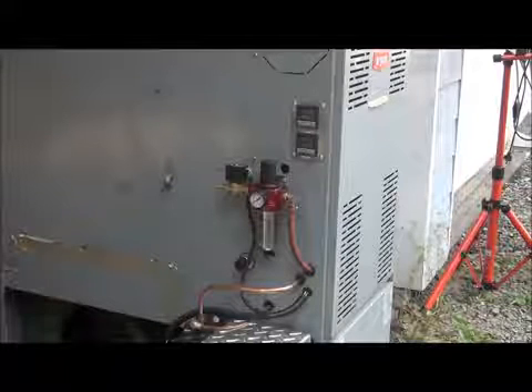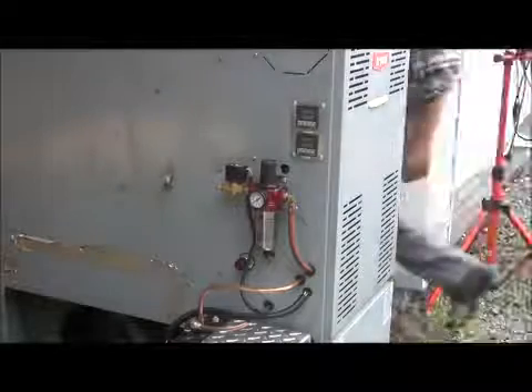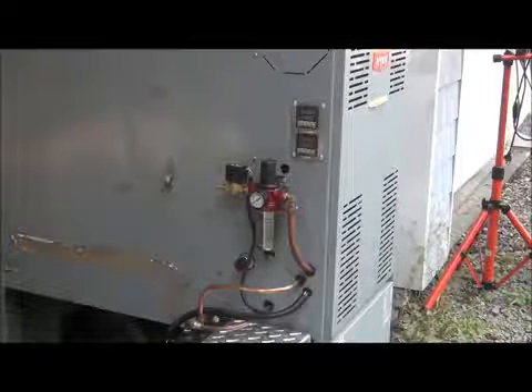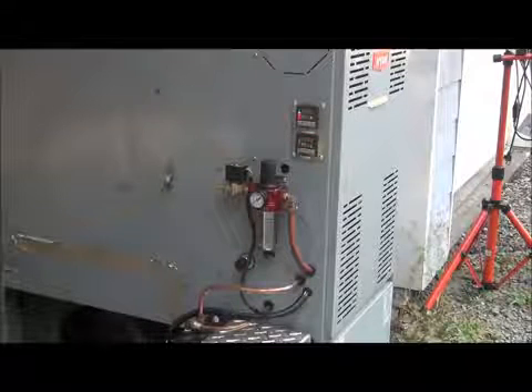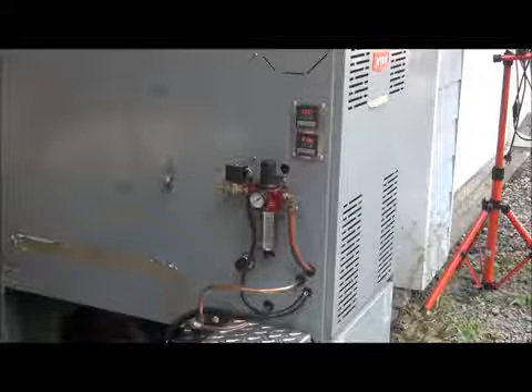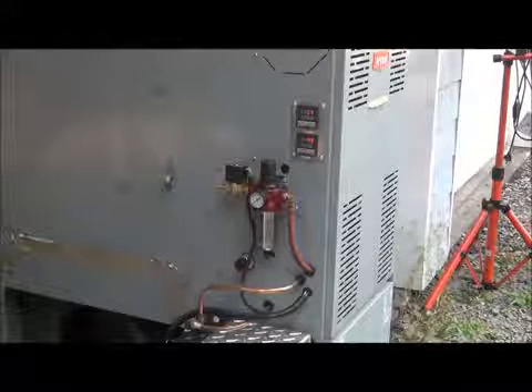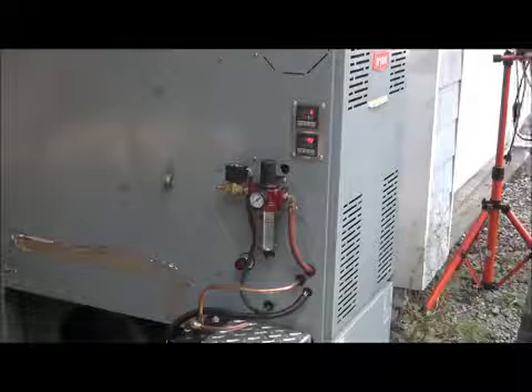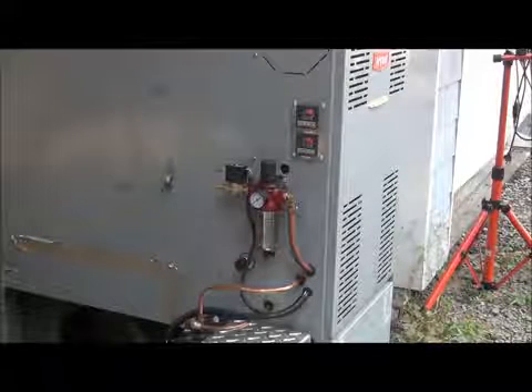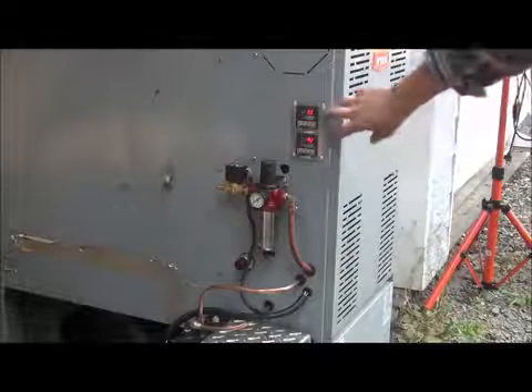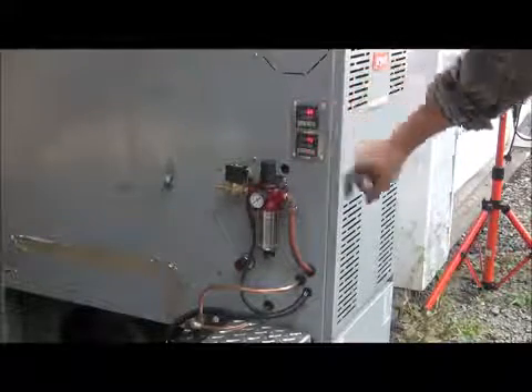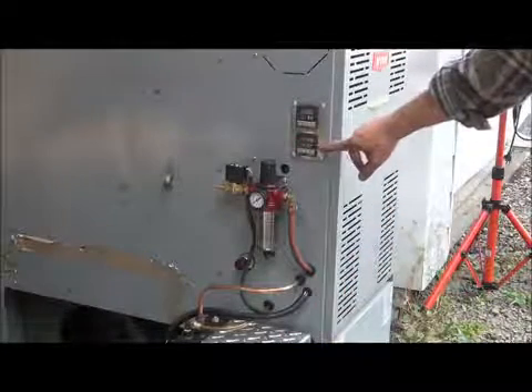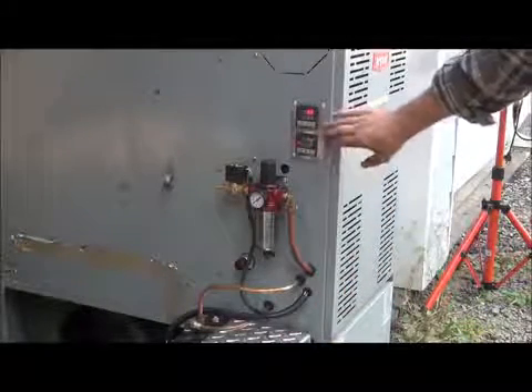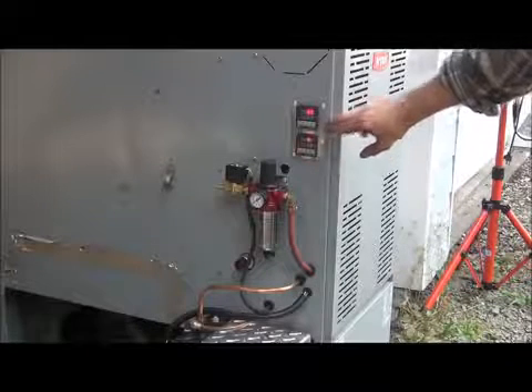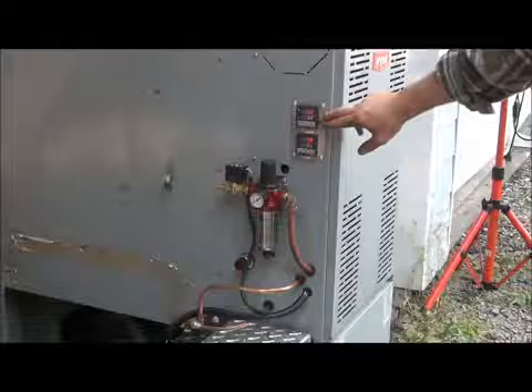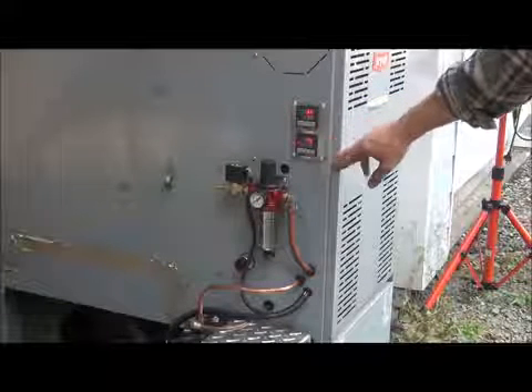Okay, we're going to go ahead and fire up the furnace. Okay, and you can see when the thermostat kicked on and requested heat, our temperature controllers are energized. This top one right here shows the temperature in our oil tank down here, and the bottom one shows the temperature in the nozzle block. And these values right here are in Celsius. So we're actually looking at about 90 degrees Fahrenheit in the tank and about 180 degrees Fahrenheit at the nozzle.